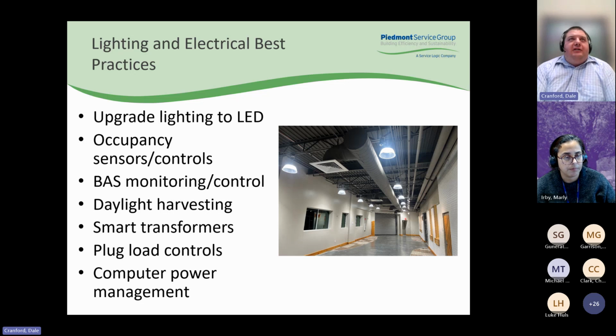Another best practice is to implement occupancy sensors and lighting controls on the building, and so those sensors, a lot of cases, can be tied to the building automation system to help tell the system to maybe go into a setback temperature for additional energy savings on your HVAC system. Putting overall controls on the building from the BAS so you can schedule your lights on a similar schedule to your HVAC system.